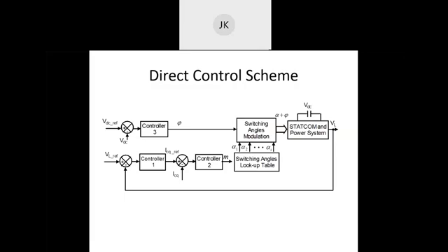If there is excess reactive power in the system, regarding the output voltage of the inverter — its application of multi-level inverter is in STATCOM also — if the voltage of this multi-level inverter is less than the load voltage, reactive power will flow from load to source. So by varying the output voltage of this inverter, we can exchange reactive power with the load or with the PCC.